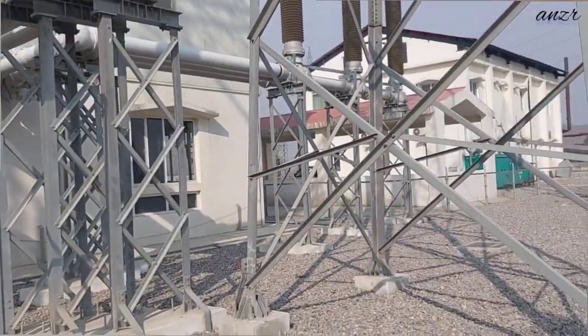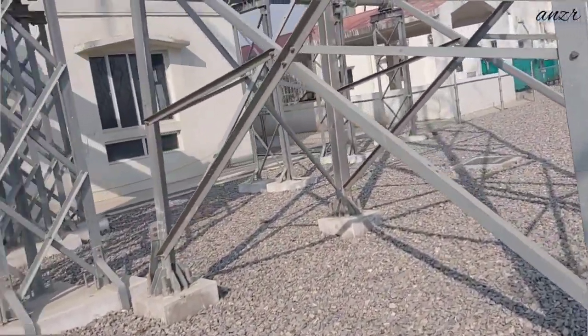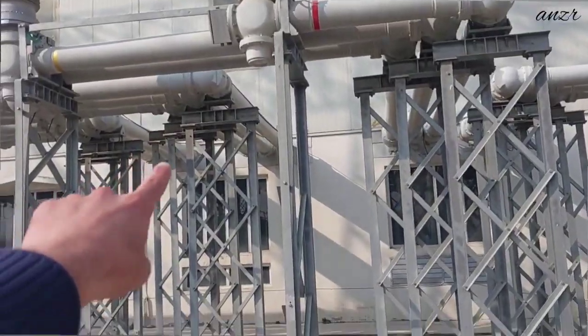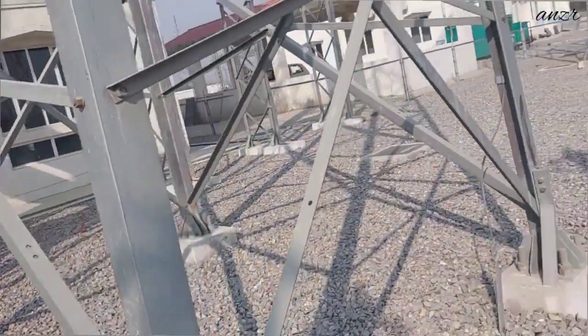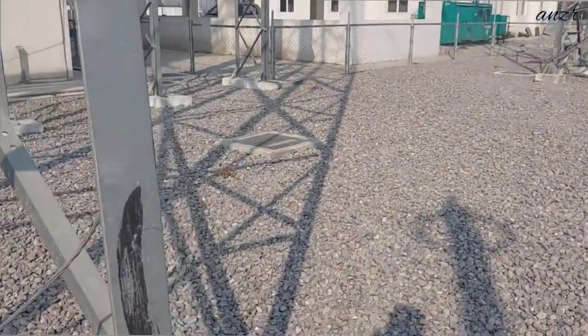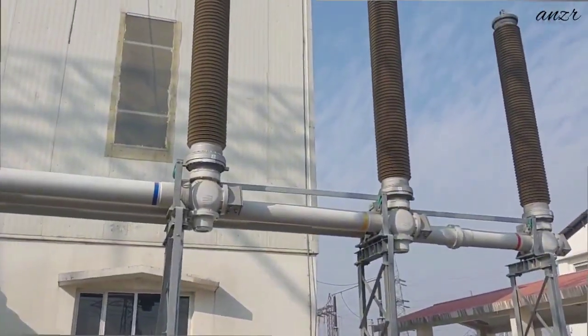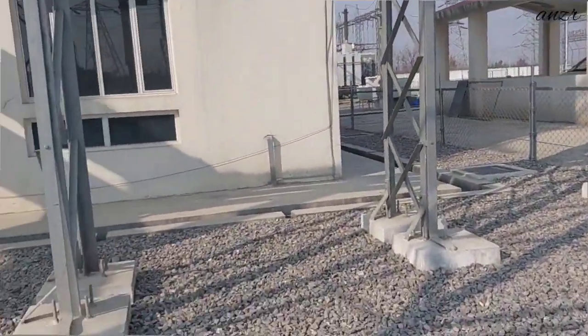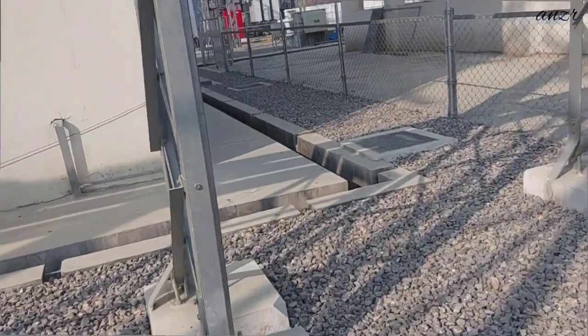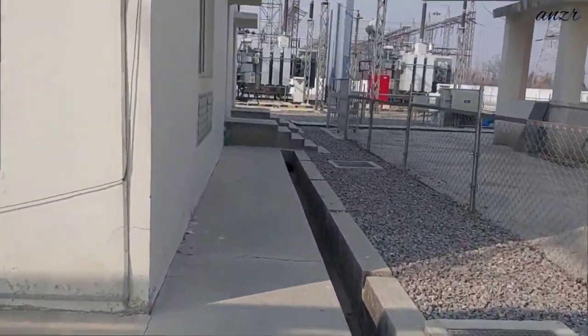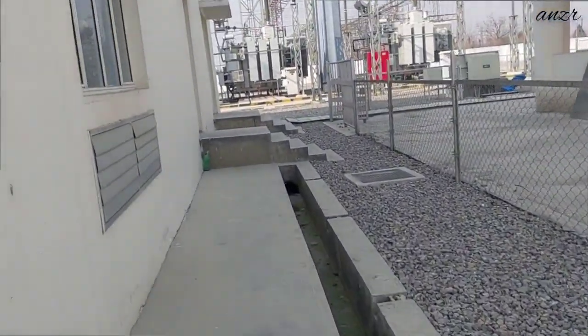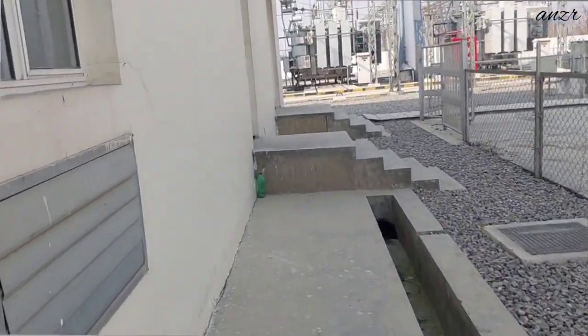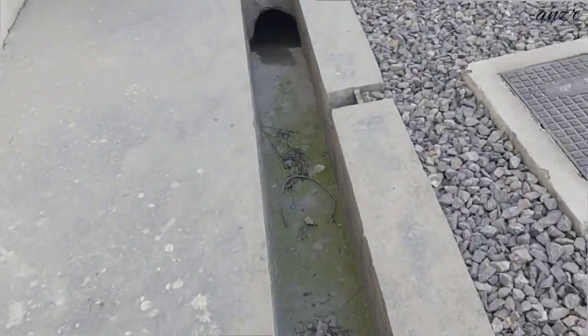After that these buses go inside, this is the yard of the circuit breaker. We will go and enter the circuit breaker section of this grid station. It is not like those AIS grids where the circuit breakers are outside in the open atmosphere, so here they are put in the building, the GIS building.